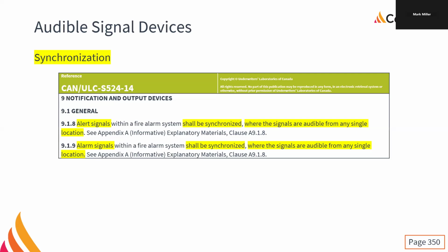Now, it doesn't have to be synchronized across an entire building, right? That's just not worth the effort. Synchronization, we're talking about when it's audible or visual from any single location. So wherever you stand, it's clear. That's all that matters for synchronization.